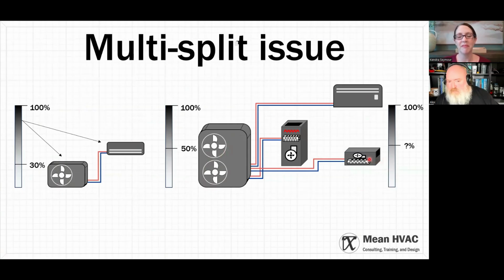So if this is a third, and only one of them calls, it's going to get half. That's more than a third, so it's given more cooling than it's actually designed for. They actually have to bleed off some refrigerant into the units that aren't running to make that happen. So the ability of your indoor units to ramp down is severely hindered by using this type of system. There are applications where they absolutely work, but there are a lot of applications where a different setup would have worked and this won't.